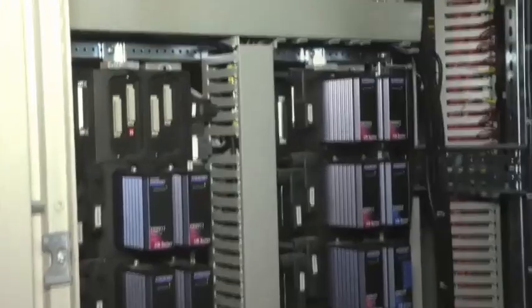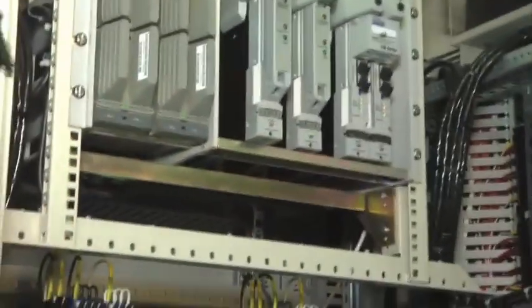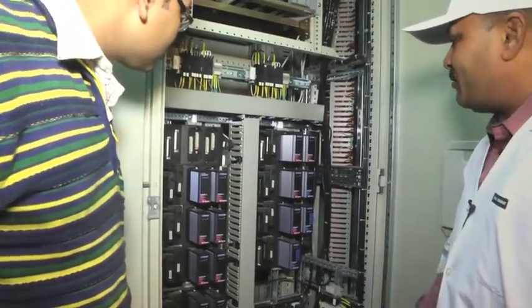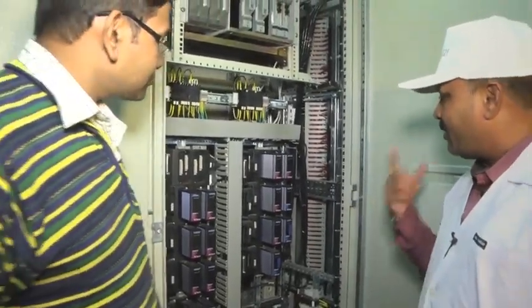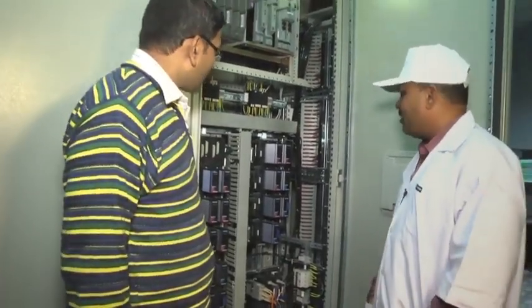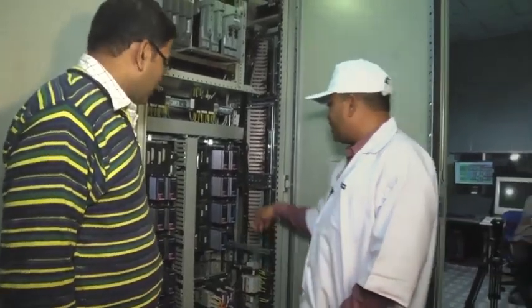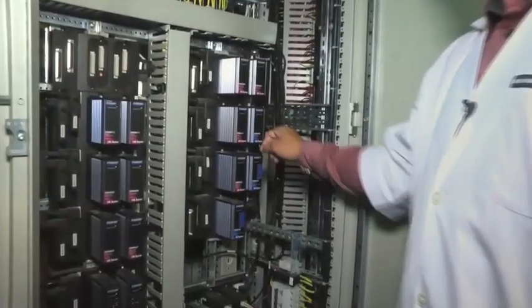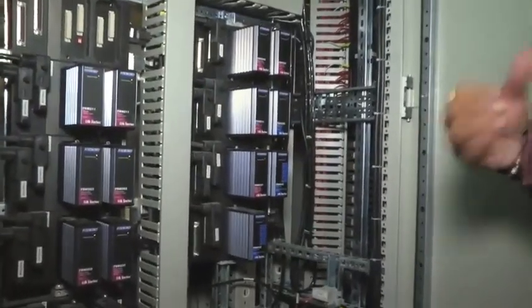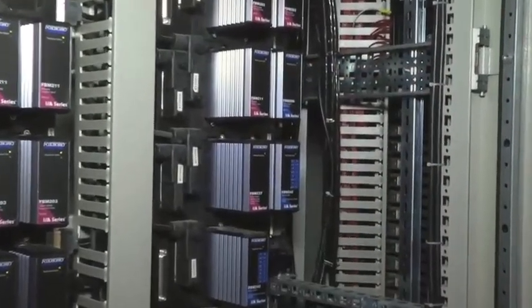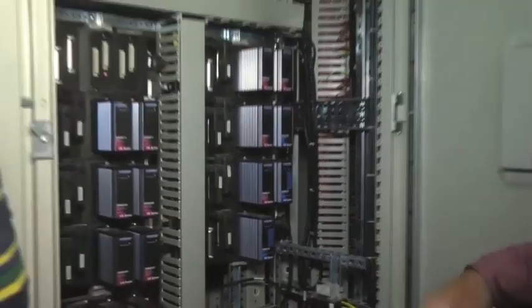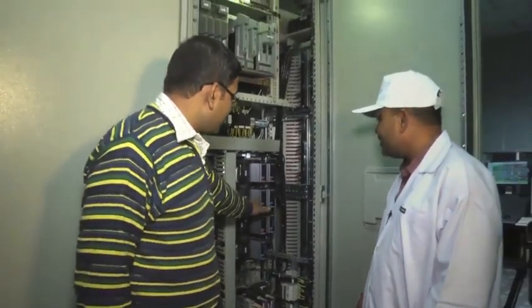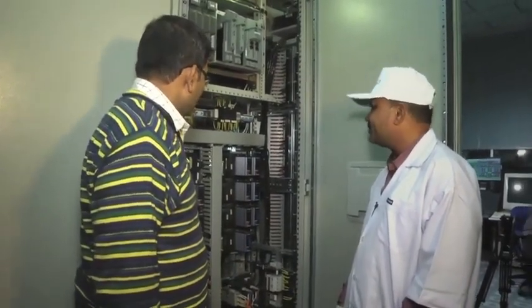Okay. And this is the node bus. By means of the node bus, the control processors communicate with the field instruments. And these are different types of FBMs. There are two different types of field inputs that come to the DCS systems: one is analog input and one is digital input. The blue colored FBMs indicate the digital inputs coming from the field, and magenta colored ones indicate the analog inputs. These are the architectures of the DCS systems. So both the analog as well as the digital inputs are handled in this particular system. Wonderful. Thank you.